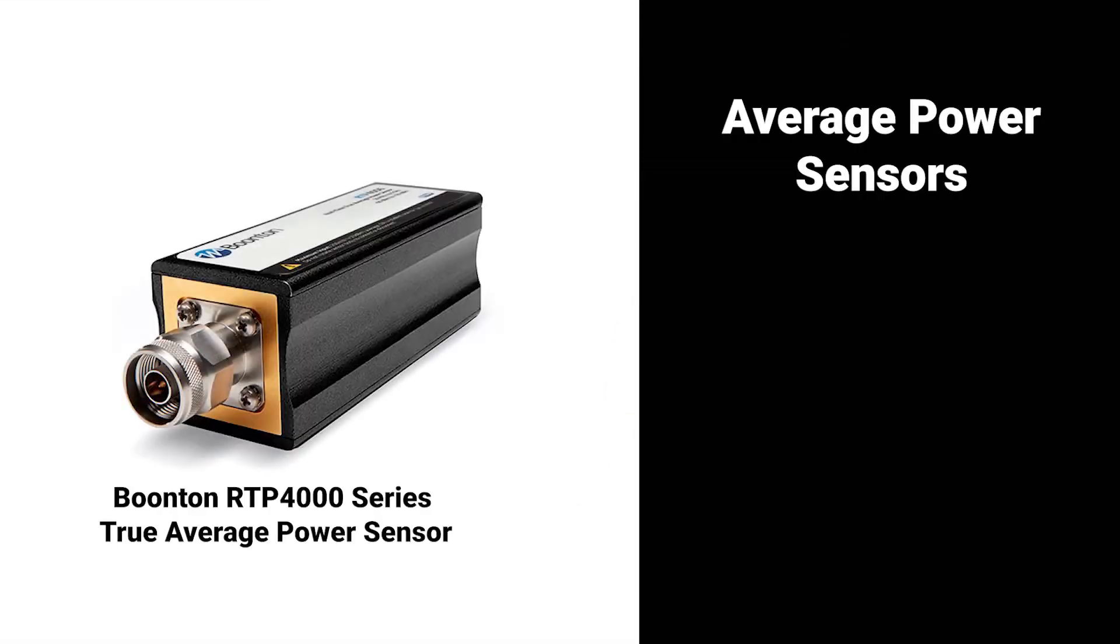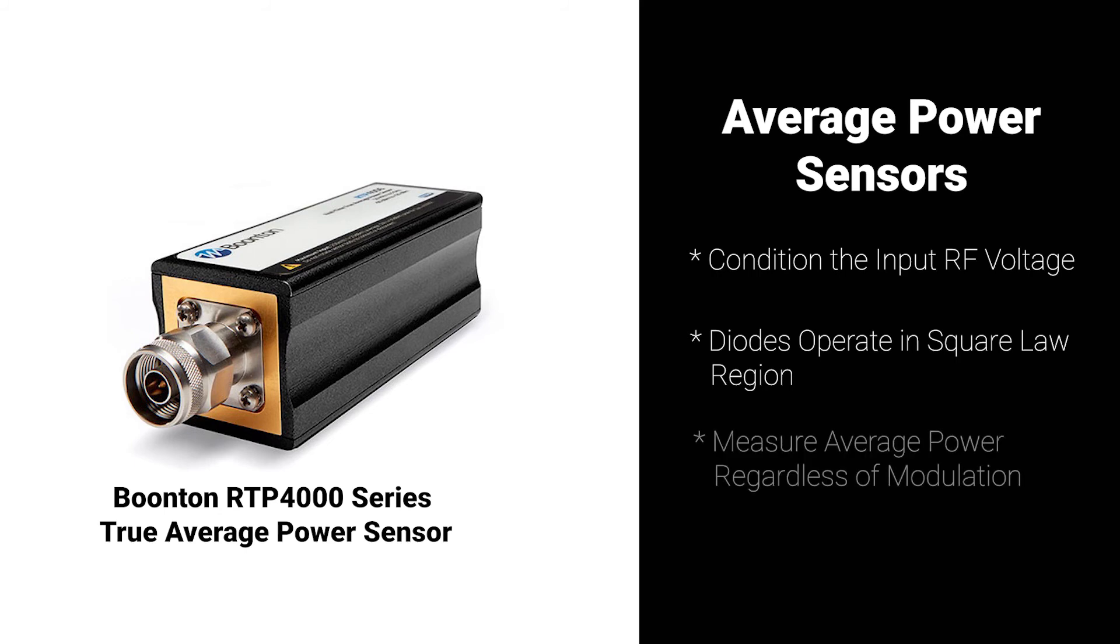Average power sensors condition the input RF voltage, which force diodes to operate in their square law region. This enables them to accurately measure average power of signals virtually regardless of modulation.